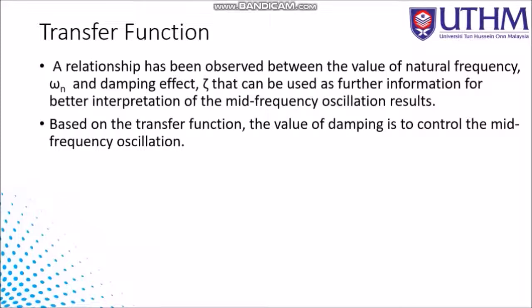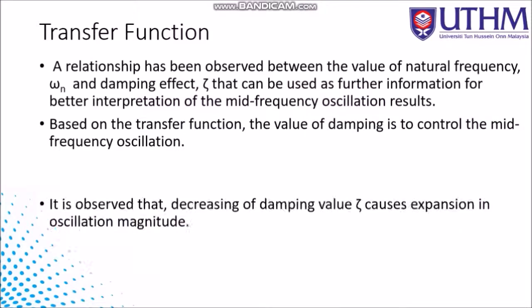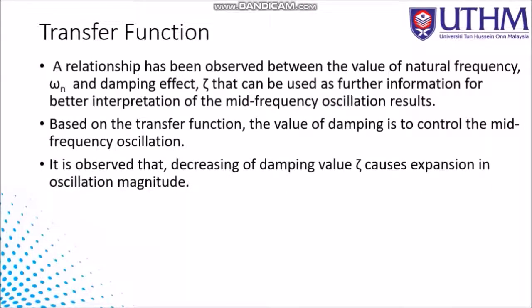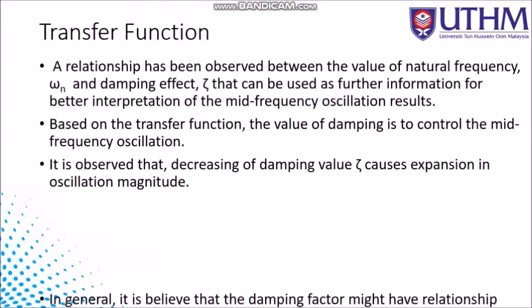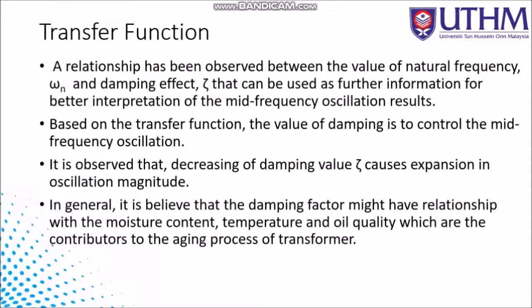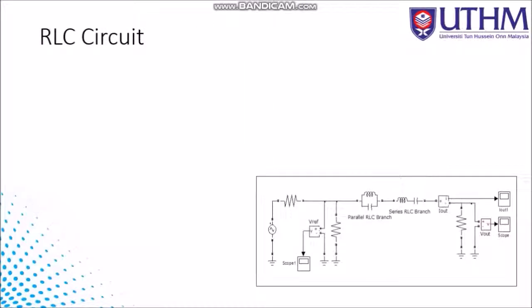A relationship has been observed between the value of natural frequency and the damping effect, which can be used for better interpretation of the mid-frequency oscillation result. Based on the transfer function, the value of damping controls the mid-frequency oscillation. It is observed that a decrease in damping value causes the expansion in the oscillation magnitude. It is believed that damping factors may have a relationship with moisture content, temperature, and oil quality — contributors to the transformer aging process.